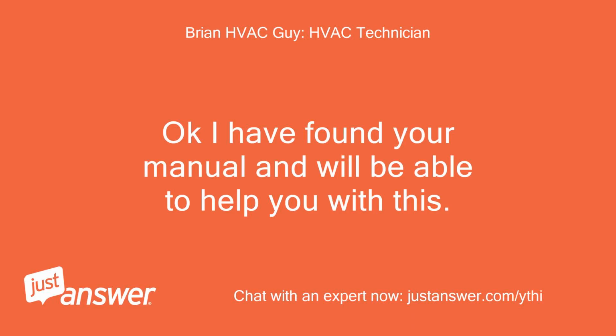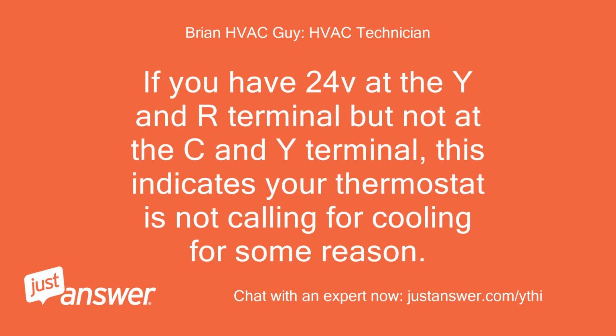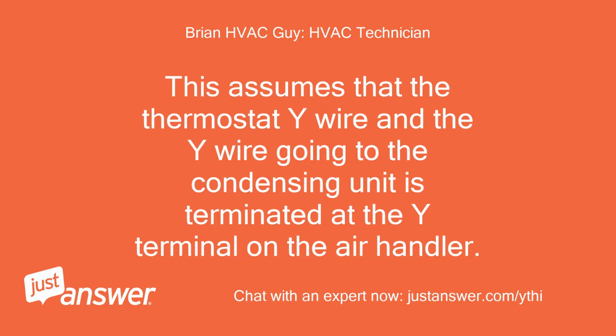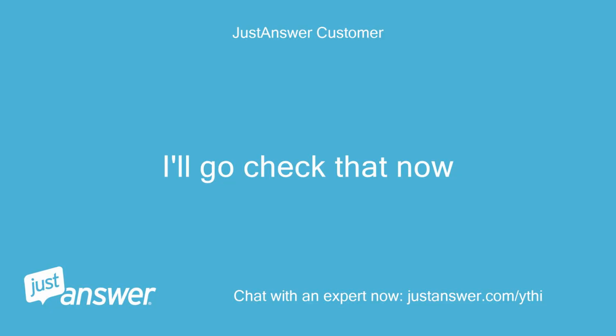Okay, I have found your manual and will be able to help you with this. If you have 24V at the Y and R terminal but not at the C and Y terminal, this indicates your thermostat is not calling for cooling for some reason. This assumes that the thermostat Y wire and the Y wire going to the condensing unit is terminated at the Y terminal on the air handler. I'll go check that now.